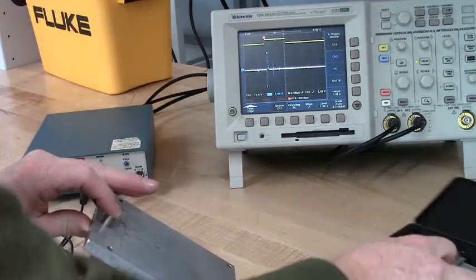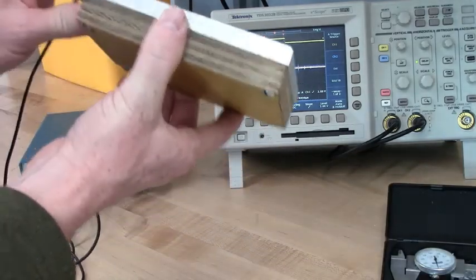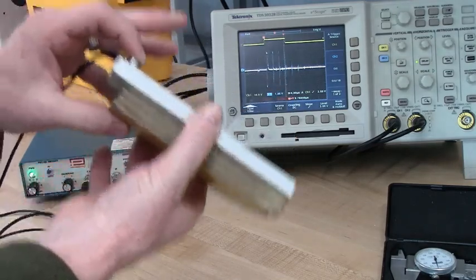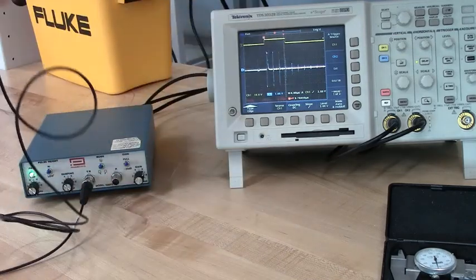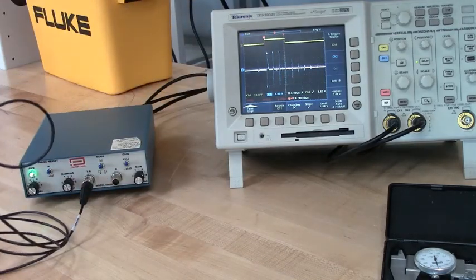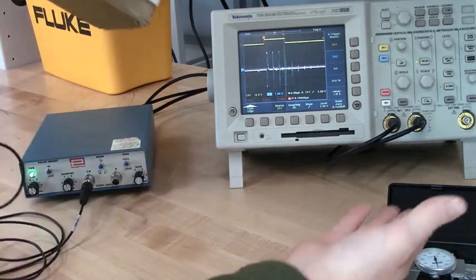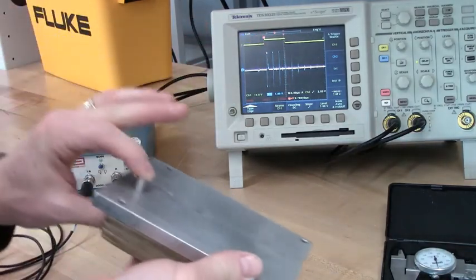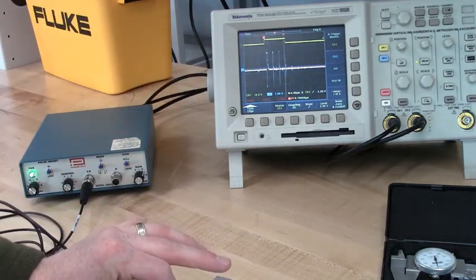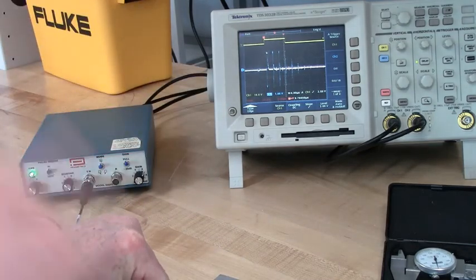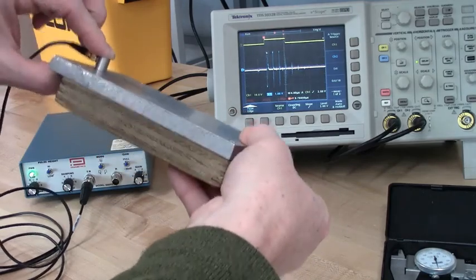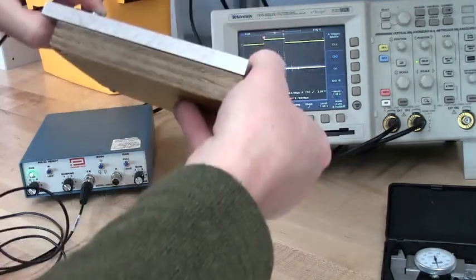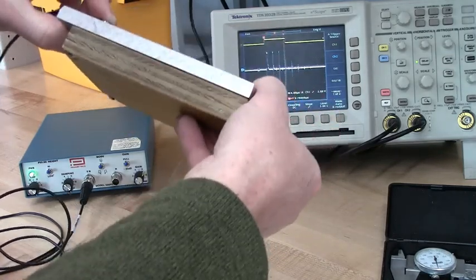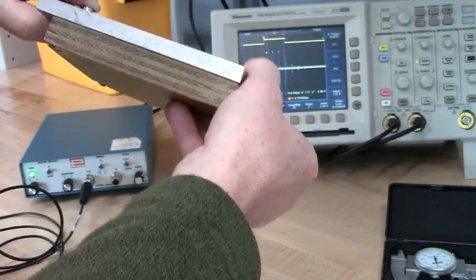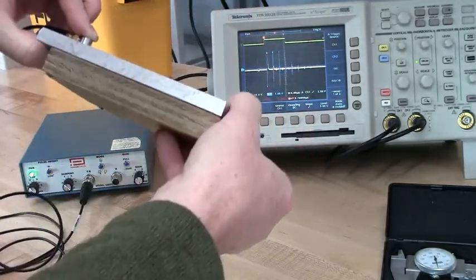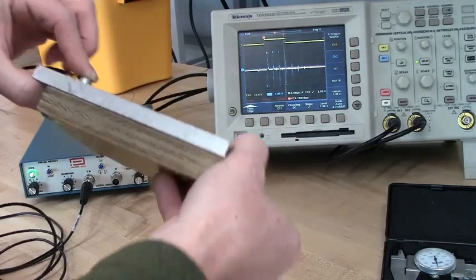I have this caliper here to do that with, and we can measure the time it takes. Now remember, it's going to be the time it takes to go through and come back. We can get that thickness here, and we can get the time it takes here. So from that, you're going to be able to determine the speed of sound. And this is aluminum. You can go online, something like Engineer's Toolbox, find a speed of sound for aluminum for longitudinal wave speed, and compare it. Make sure that we're in the ballpark. And then we're going to use that speed of sound to find the depth of the part that's been machined out.